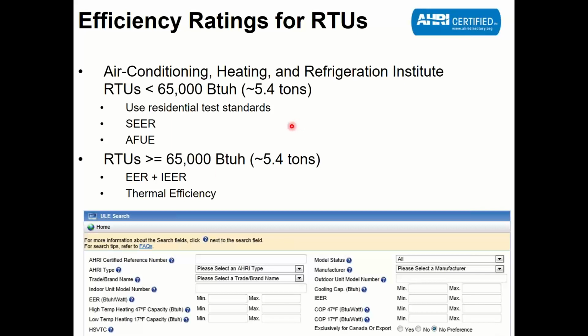And for the gas heating section, it would be AFUE, Annual Fuel Utilization Efficiency in terms of percent. SEER is Seasonal Energy Efficiency Ratio. When we get to the bigger stuff, which would be over 5 tons, then what I have for cooling is 2 ratings. Well, actually for residential, I have EER and SEER also. Everybody just ignores EER though. But for commercial, I still have 2 ratings, EER and IEER. EER is Energy Efficiency Ratio.